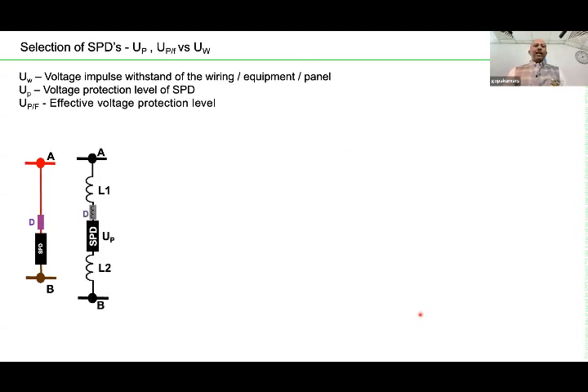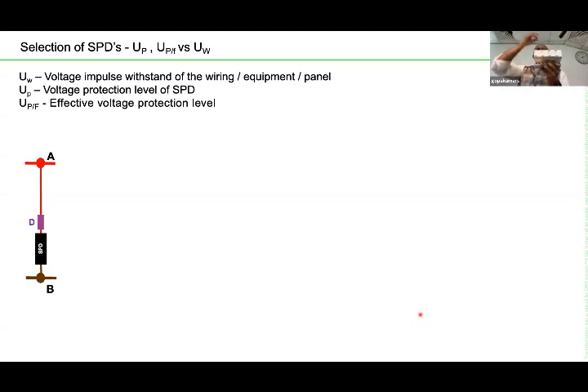Now imagine you have an SPD like this, A and B, let's say line and neutral. Between line and neutral you have a wire, because the SPD is mounted on a DIN rail, not this one. You take a wire from the phase terminal and connect it to the SPD. Then from the SPD, the earth wire is again connected. So something like this. And sometimes in between the line and the SPD, you need an HRC fuse as well.